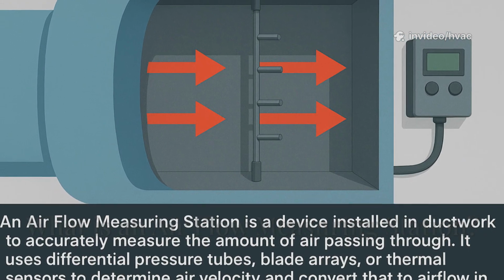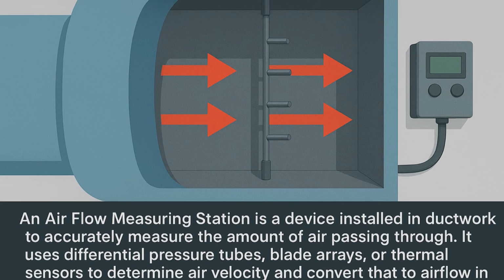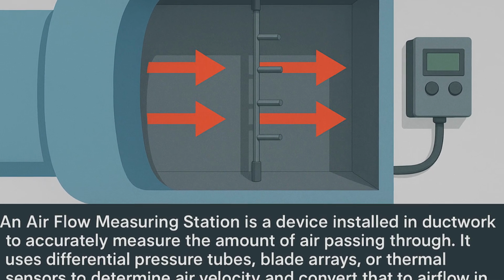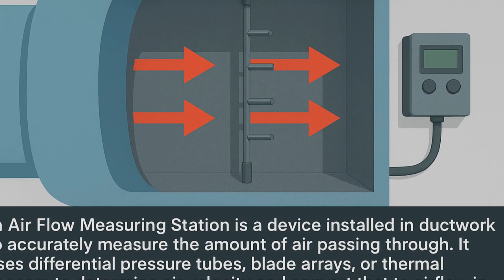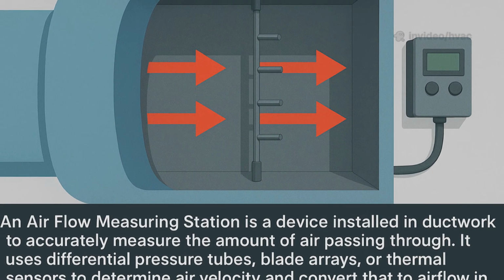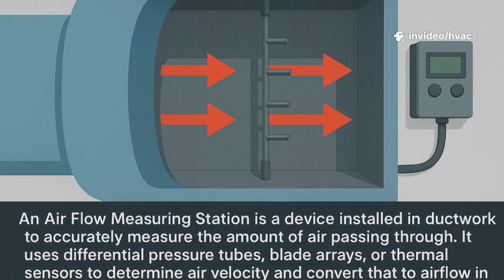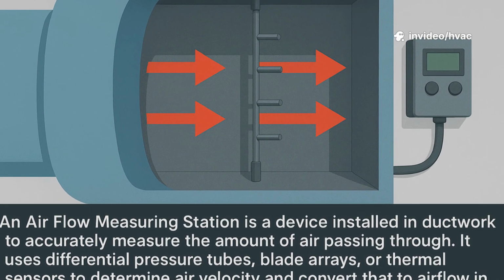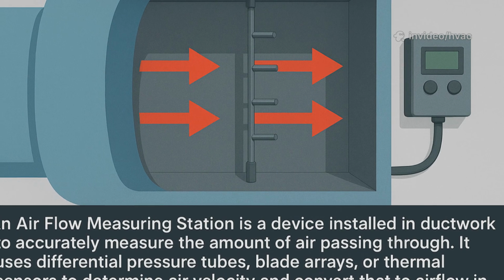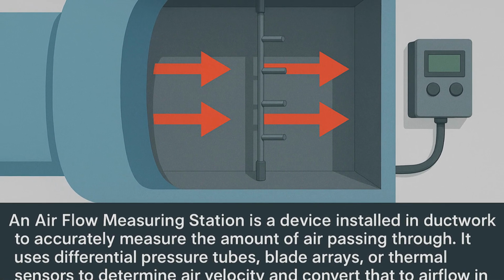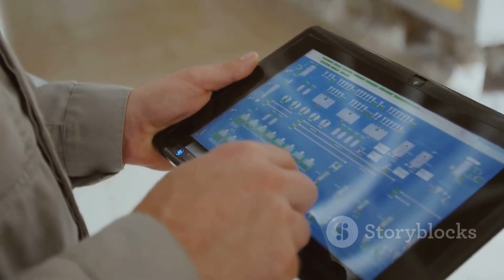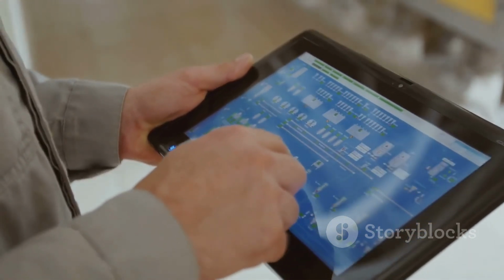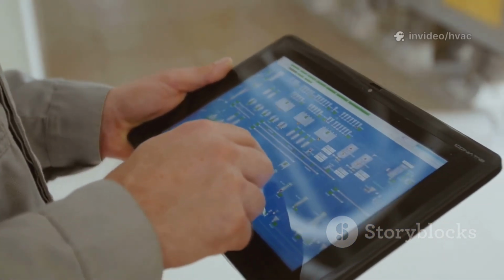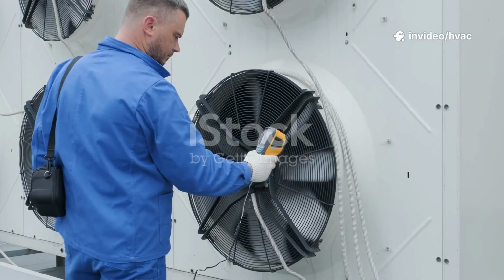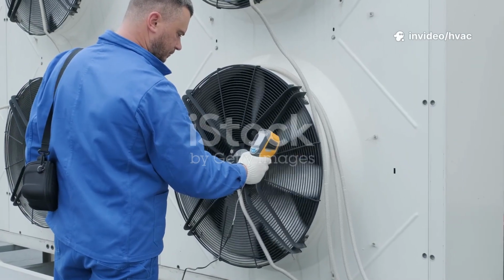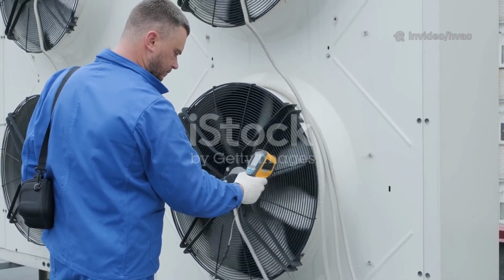An airflow measuring station is a device installed in ductwork to accurately measure the amount of air passing through. It uses differential pressure tubes, blade arrays, or thermal sensors to determine air velocity and convert that to airflow in cubic feet per minute, or CFM, or liters per second, which we call LPS. These stations are essential for maintaining proper ventilation, energy efficiency, and indoor air quality in buildings. Regular calibration and maintenance ensure their accuracy and reliable performance over time.